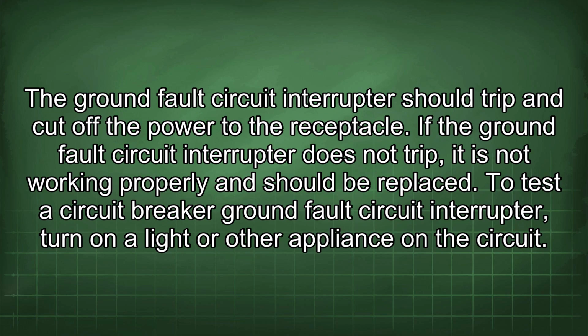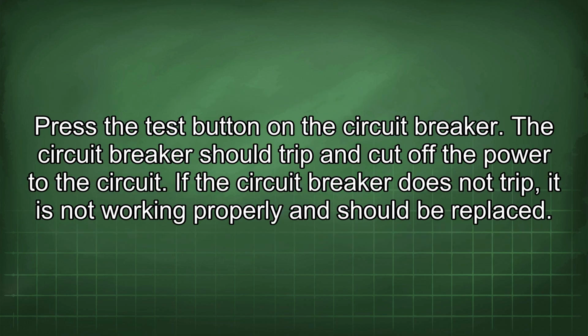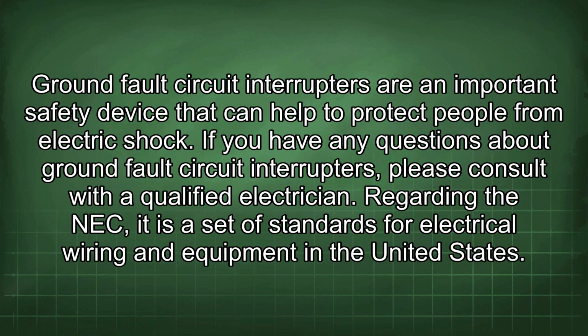To test the circuit breaker ground fault circuit interrupter, turn on a light or other appliance on the circuit. Press the test button on the circuit breaker. The circuit breaker should trip and cut off the power to the circuit. If the circuit breaker does not trip, it is not working properly and should be replaced. Ground fault circuit interrupters are an important safety device that can help to protect people from electric shock. If you have any questions about ground fault circuit interrupters, please consult with a qualified electrician.